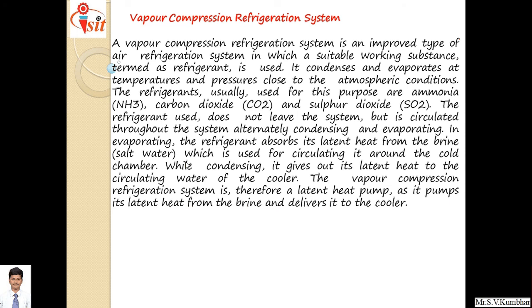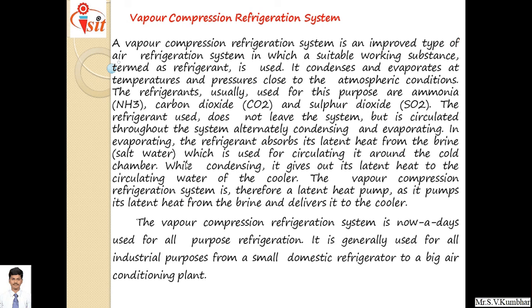While evaporating, the refrigerant absorbs its latent heat from the brine, that is, the salt solution used for circulating around the cold chamber. When condensing, it gives out its latent heat to the circulating water in the cooler. The vapor compression refrigeration system is therefore a latent heat pump, as it pumps latent heat from the brine and delivers it to the cooler. It is nowadays used for all purposes of refrigeration, generally for all industrial purposes, from a small domestic refrigerator to a big air conditioning plant.